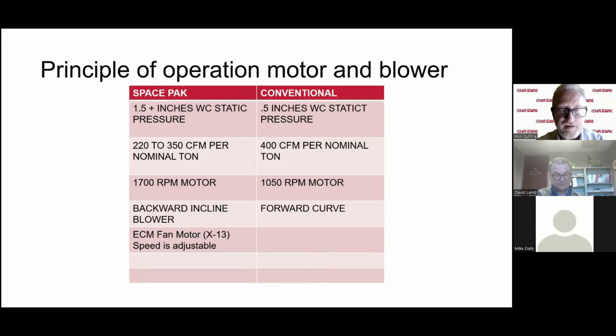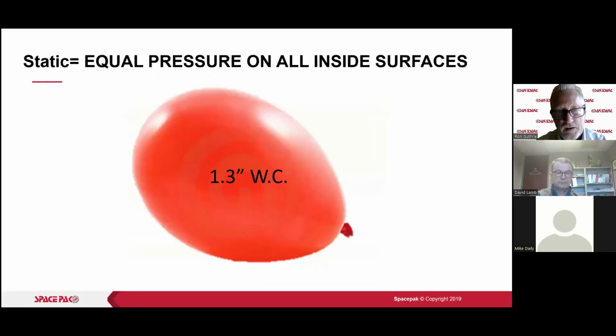So we get all sorts of things coming in, but we've had guys wonder why they couldn't put a standard air handler in place of our system. God knows there are probably guys out there who have tried. The problem is those standard air handlers will not operate up to the static pressure levels that our unit will operate to. All right, and then also our motor is an ECM fan motor X13. Okay, but we're controlling that as a variable by the signal that we send, the volt DC signal that we send to that motor. Okay, and we'll talk all about that as we move forward here.